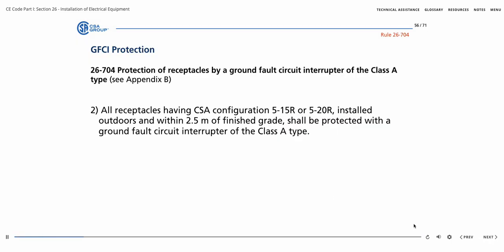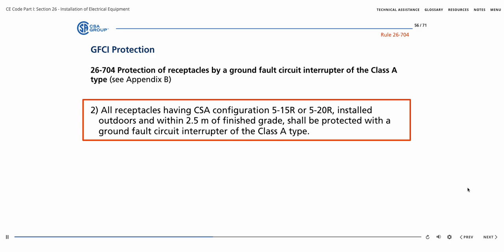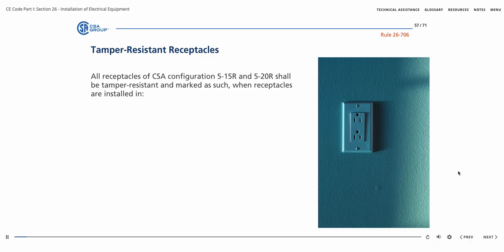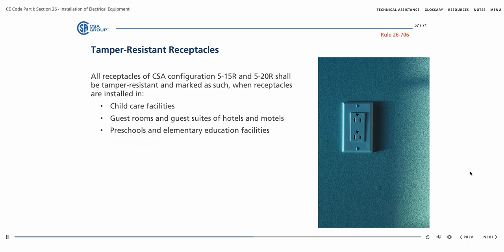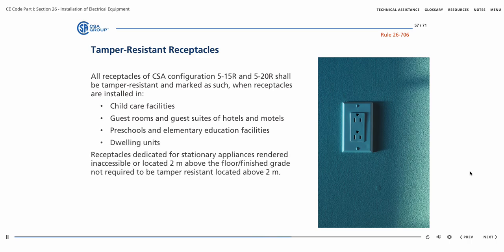Rule 26-704, Sub-Rule 2, states that all outlets installed outdoors less than 2.5 meters from grade are required to have GFCI protection. All receptacles of CSA configuration 5-15R and 5-20R shall be tamper-resistant receptacles and marked as such according to Rule 26-706 when receptacles are installed in child care facilities, guest rooms and guest suites of hotels and motels, preschools and elementary education facilities, and dwelling units. Receptacles dedicated to stationary appliances, such that the receptacle is rendered inaccessible, or those located above 2 meters above the floor or finished grade, are not required to be tamper-resistant.